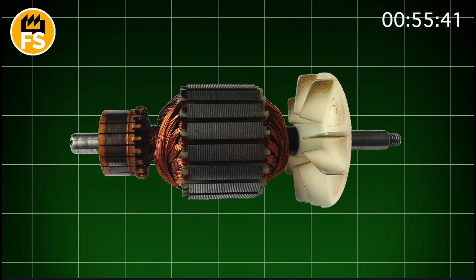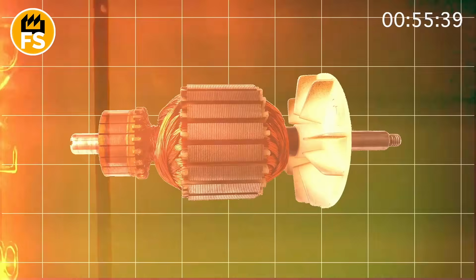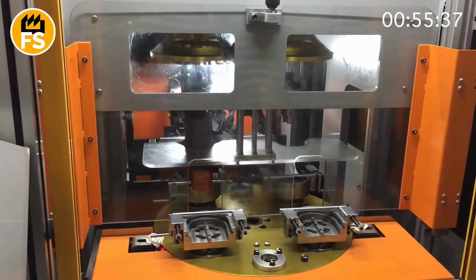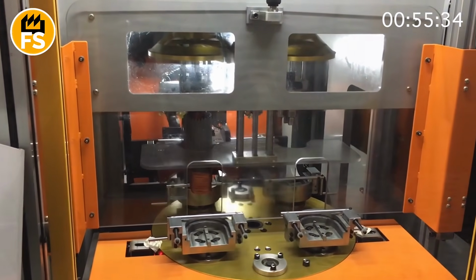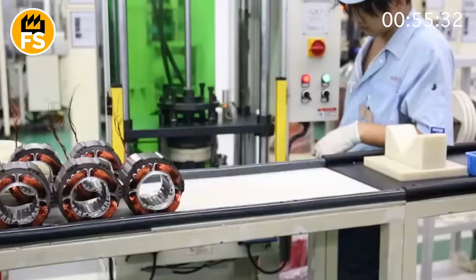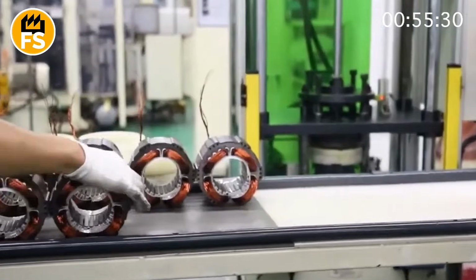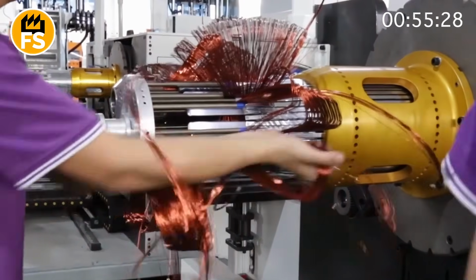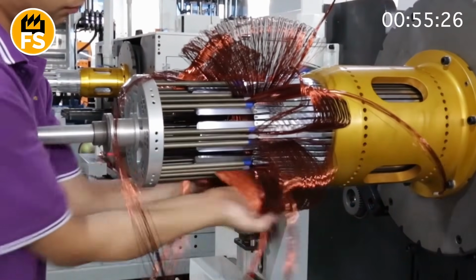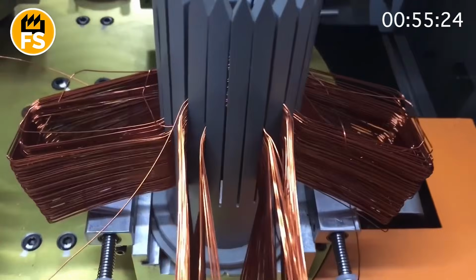Before starting the winding, the stator frame is thoroughly prepared. The slots are lined with special insulating liners, like nests for the wire. These are materials that withstand high temperatures, vibrations, and electrical loads. And only when they are sure that the insulation is perfect, the winding machine is started.